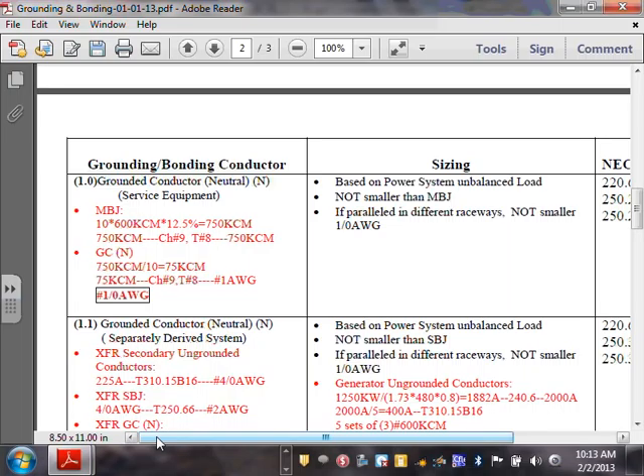Okay, this is how we size the main bonding jumper. The way we size a main bonding jumper, you take the number of sets in parallel, multiply them by the size of the service conductors, right? And then multiply them by this magic number, 12.5%. Cool? So if you do that, you end up with 750 kcm. If you don't know if 750 kcm is a standard conductor or not, where are you going to go? Chapter 9, Table 8. If you guys go there, which is so all of you are masters, past the journeyman master, you know where Chapter 9, Table 8 is, you're going to find 750.